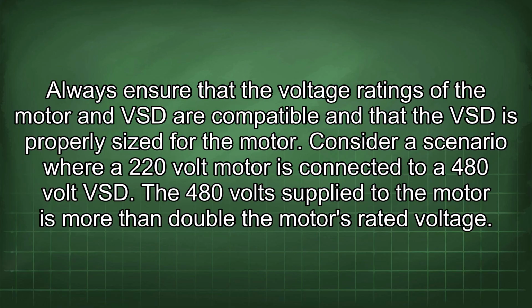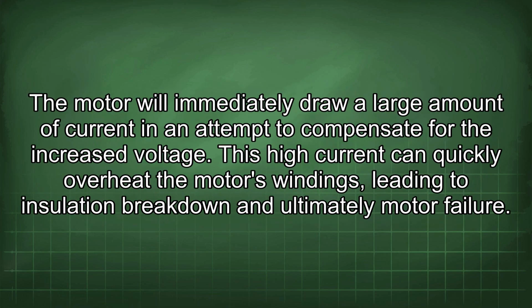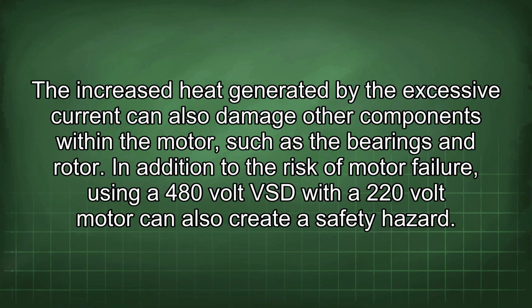for the motor. Consider a scenario where a 220-volt motor is connected to a 480-volt VSD. The 480-volt supply to the motor is more than double the motor's rated voltage. The motor will immediately draw a large amount of current in an attempt to compensate for the increased voltage. This high current can quickly overheat the motor's windings, leading to insulation breakdown and ultimately motor failure.